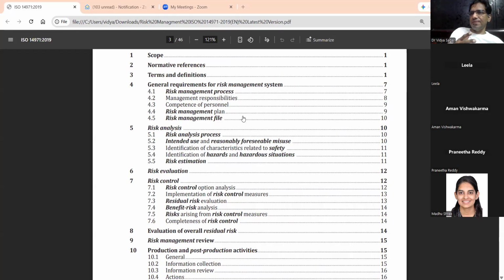So how this has traveled: from risk management, it condenses to residual risk. Residual risk, you are correlating with the adverse events, or some events that are not good to the patient, could be side effects, events, serious events. And that you are conveying to the end user. For us, the end user is not the patient. For us, the end user is the doctor, because we are not selling OTC products, over the counter. Of course, some medical devices are sold over the counter. But for the high risk category, where even the residual risk carries high risk, we convey them in the form of the IFU. As I said, 3-4 categories will be provided: warnings, precautions, contraindications.